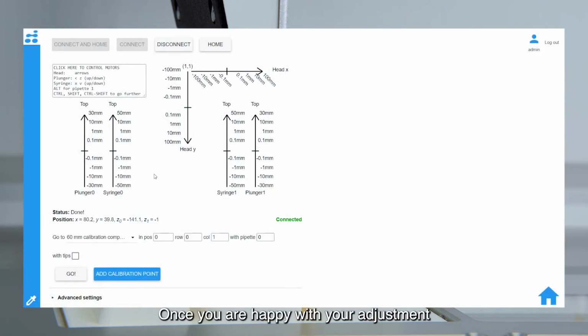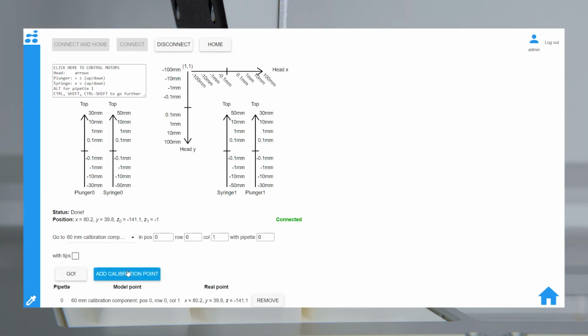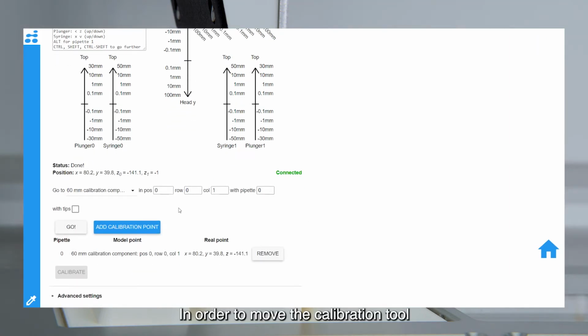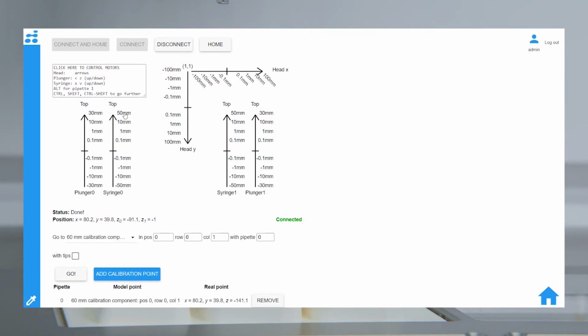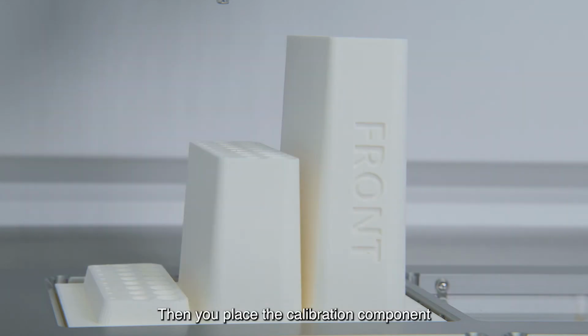Once you're happy with your adjustment in the Z axis, you need to check that the Y and X axis are aligned as well. If not, you can adjust it on the graphs here or use the shortcuts on the top left corner. Once you're happy with your adjustments, you press Add Calibration Point. In order to be able to move the calibration tool, raise the pipette module 50 millimeter. Then you place the calibration component in a different position. This time you will do it in position 3, which is the top right corner.